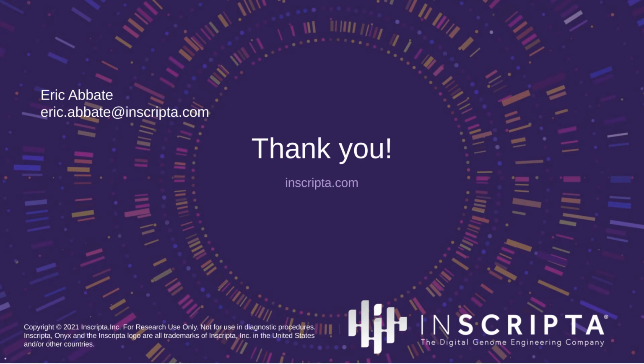Our first question asks, can you talk about the generate step in more detail? Yes, I think that's in reference to the actual building of the library, which happens on the instrument. I can give a brief overview of what happens on the instrument during the build process, but I would also encourage you to look at some really cool videos we have on our Inscripta website. There's a nice video called Onyx Instrument Tour that goes through all of the steps in a little bit more detail. But basically, for the generate part, what happens on the instrument is you put the consumables and reagents onto the deck along with the cells that you want to introduce your library in.